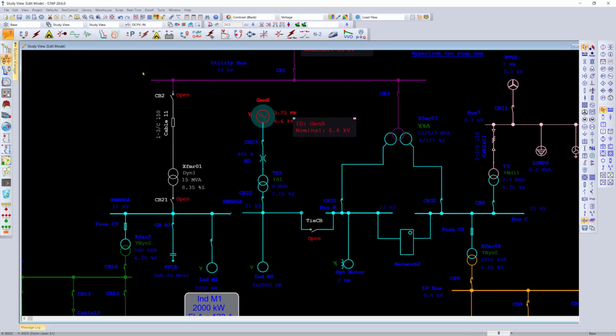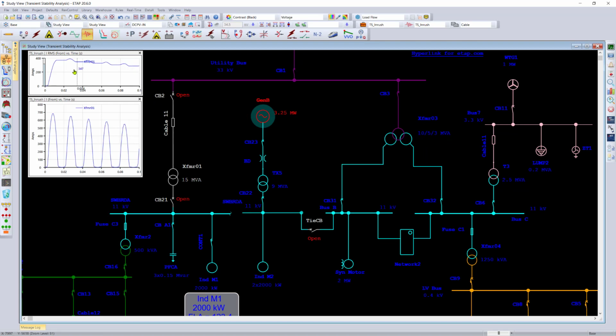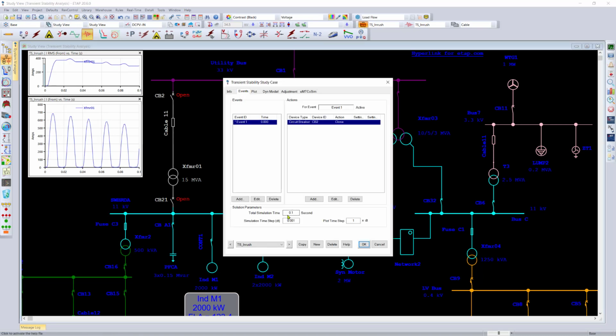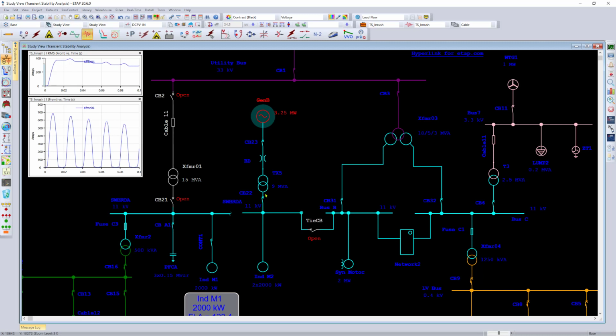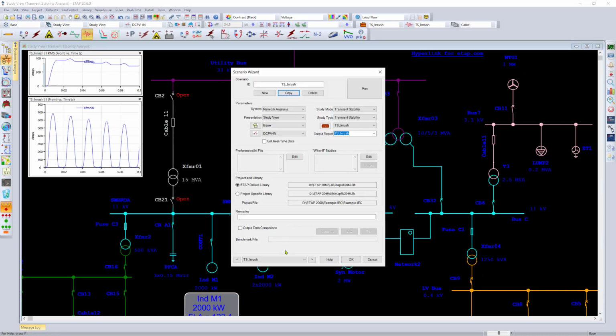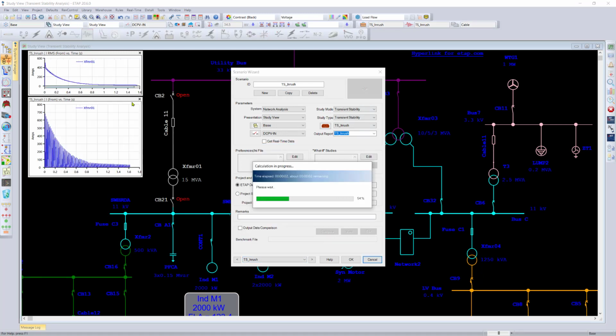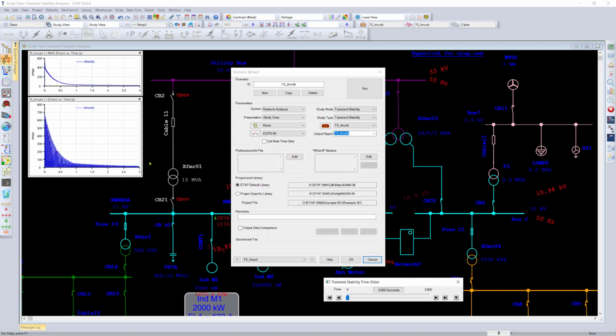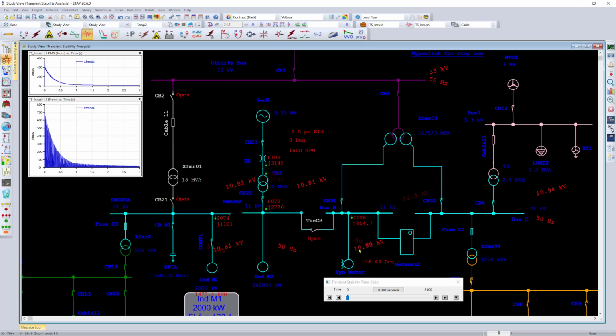The plot view has also been enhanced for transient stability, where the program allows you to not only plot the transformer inrush curve, but also allows you to plot the transformer inrush RMS curve at the same time. Simply go inside the study case, set the time frame that you would like to run the simulation for, and go ahead and perform the actual study directly from ETAP. You can use any of the scenarios or obviously run the calculation directly inside the program and see the visualization through a live chart that includes the inrush and the RMS current directly onto the diagram.